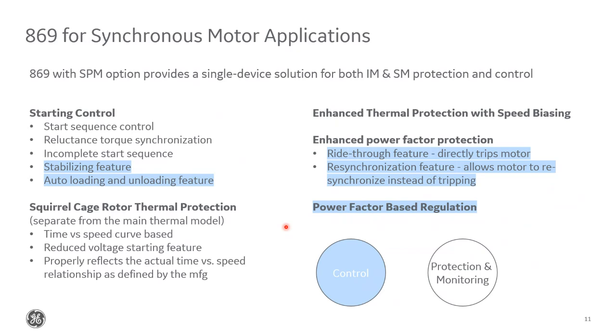Some of these, like start sequence control, incomplete start, and power factor regulation, were brought over from the SPM, in addition to other protection elements like loss of excitation, out of step, and so on. But we also added some new, more advanced features that I want to touch on as well, like stabilizing and auto loading and unloading, squirrel cage, rotor thermal protection, speed biasing, and power factor protection enhancements.